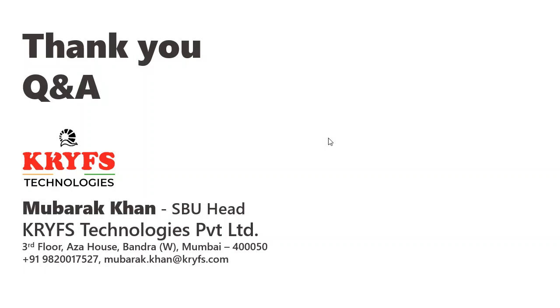If you have any technical question or any doubt, we can do that. Yes, please. Can it connect with SCADA system? Very good, interesting question. Answer is simple, yes, we can connect to SCADA system. We have all the connection possibilities which may be required, like RS-485, IEC 60870, fiber optic, or any other system requirement we can do. We can even have an IoT VPN which can be used for a local server within your premises. Which communication modes do you support? As mentioned, we give all the different types of outputs which may be required for the SCADA system: RS-485, IEC 60870, Ethernet, and all.